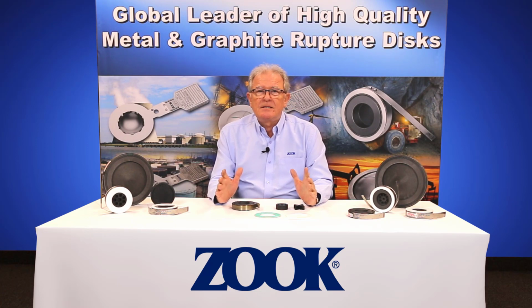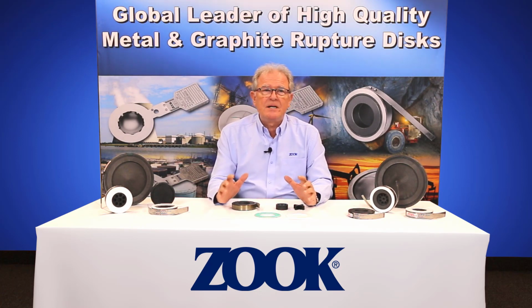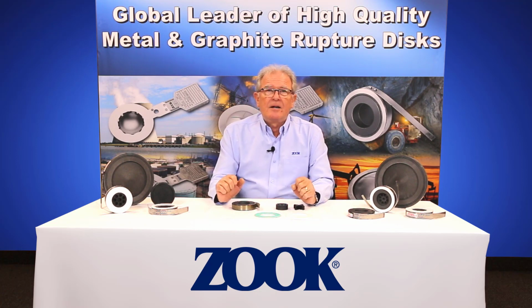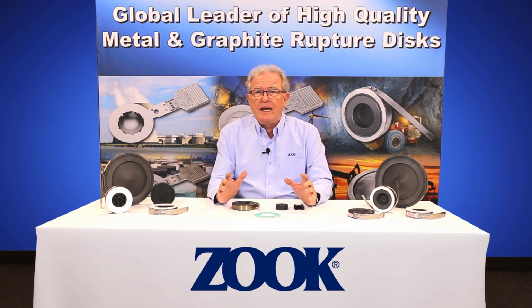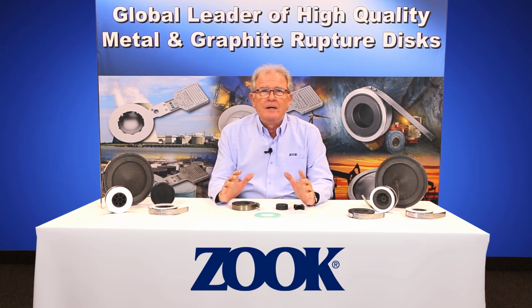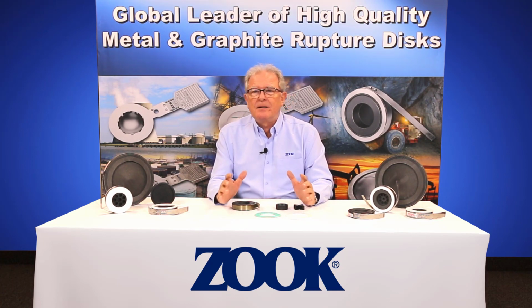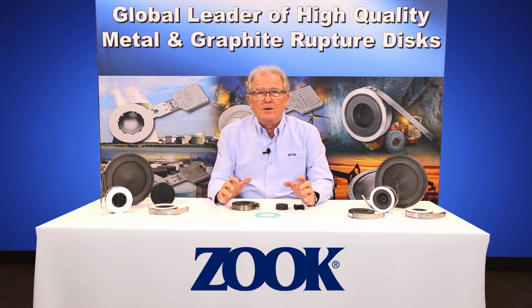In the world of rupture discs, the first law that applies to all discs, regardless of type and material, is to produce an impermeable barrier about which a differential pressure can be created. Graphite, in the form that ZOOK receives it in, has a porous structure, equivalent to some 8 to 14% porosity depending on the grade of graphite we purchase. Effectively, we start with a dense black sponge. So in order to meet the first law of rupture discs, we need to render this graphite sponge to an impervious material.